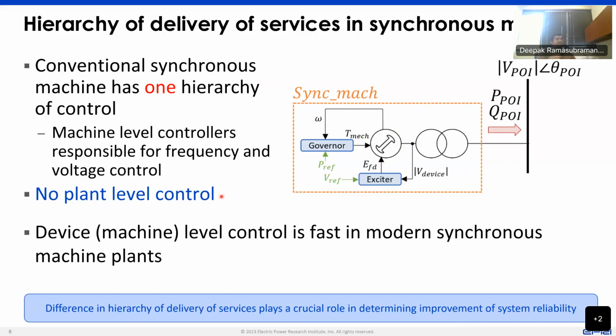Now here we are talking about our regular transient events, dynamic events that occur for 45 to 60 seconds. We're not talking about some supervisory secondary control for frequency regulation or a tertiary control for market balancing and so on. We're talking about an event that happens on the system, and we are looking at the behavior that comes about in the 20 seconds after the event has occurred. So if a machine has this kind of control, one of the reasons why it is able to provide a lot of the services that we require is, firstly, yes, natural laws of motion and the physics that it operates under, but secondly, because all of the control is at the device level and not at a higher plant level. So it's by default faster than having something at the plant level, and that difference in hierarchy can play a crucial role in determining stability of the network.